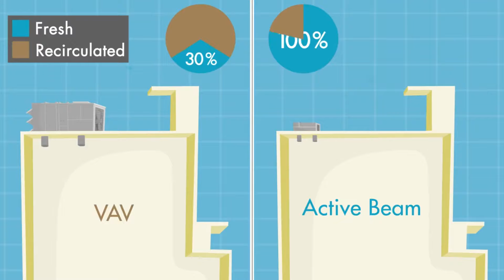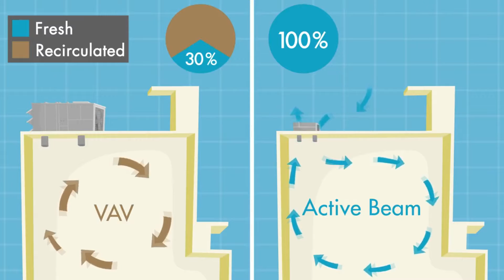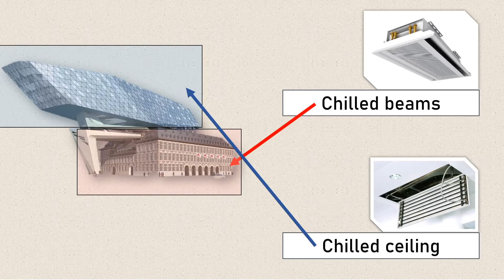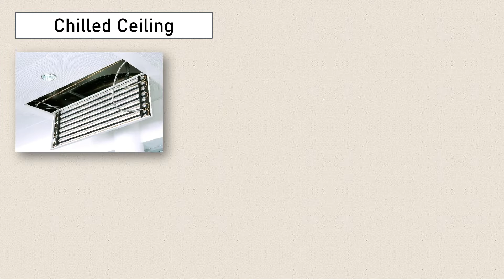Thirdly, as the total volume of air distributed is fairly small, it can be comprised of 100% outside air. This offers a fresher tenant environment with no more stale air being recirculated through the building. Fourthly, chilled beams have no moving parts or filters, making them virtually maintenance-free and far less expensive over their lifetime. While the pre-existing building used chilled beams for the heating and cooling process, the newly added building used the chilled ceiling method for heating and cooling. Chilled ceilings differ from chilled beams. A chilled ceiling is a metal sheet with water pipes running above it.